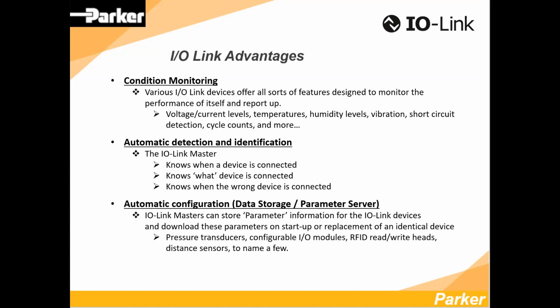Automatic configuration - like the industrial USB analogy, it's all plug and play. When maintenance replaces something, they just plug it in. This does have to be set up, but the functionality is there so that on connect, any or all configuration of that device is downloaded right to it. Think about a pressure sensor - normally maintenance has to use toggle buttons to set the set points, units, scaling, hysteresis, display orientation - there's many things. Now they just plug it in, and all that information is automatically downloaded. That's huge.